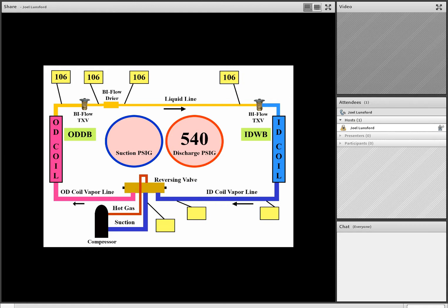In our next example, we see we have a 410A call. We have pink or rose-colored background on the gauges, and we have 401 pounds of pressure for 410A. At 401 pounds of pressure, we have a pressure temperature conversion of about 117 degrees off of the chart. We also notice we have 107 degree liquid line temperature, and the difference between 107 and 117 is 10 degrees of subcooling. In this example, our subcooling level should be between 10 to 15 degrees, and we're running about 10 to 11 degrees subcooling. In this example, our subcooling on the warm coil is normal.